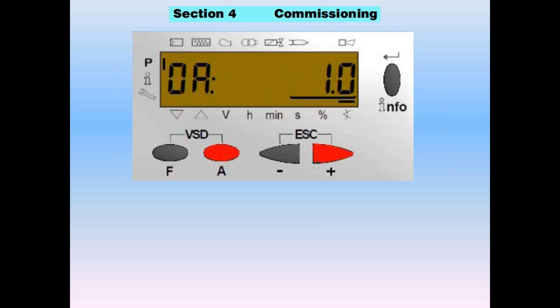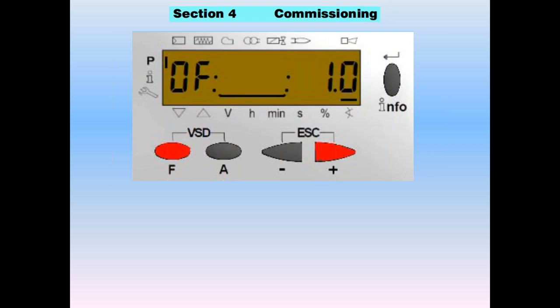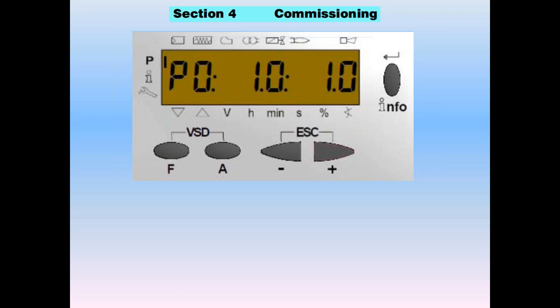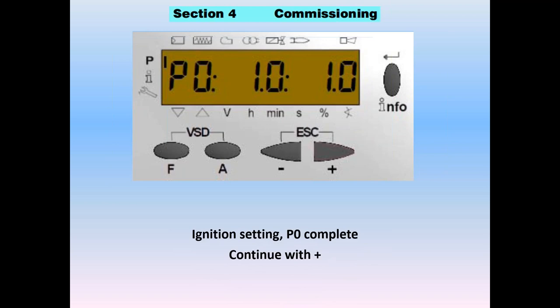The first thing prompted is the ignition settings — P0. Hold the A key and hold plus or minus to dial up what you want for the air damper setting — in this case, one degree. Release it, then hold the F key and go plus or minus to dial up the fuel butterfly valve for the gas actuator. Here we have P0 set at one degree of gas and one degree of air for the ignition setting on the light-off of this burner.